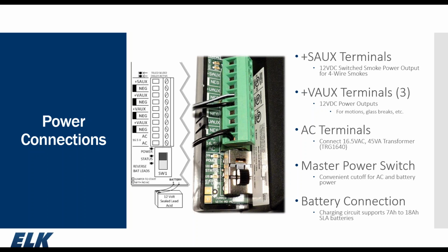The system will give you 1 amp of continuous output at any given time, and that's a combination of the SAUX, the VAUX, J16, and the data bus. So at any given time, the M1 has 1 amp continuous output. When the system goes into alarm, you can get up to 2.5 amps of current out of it with the additional current coming from the battery.